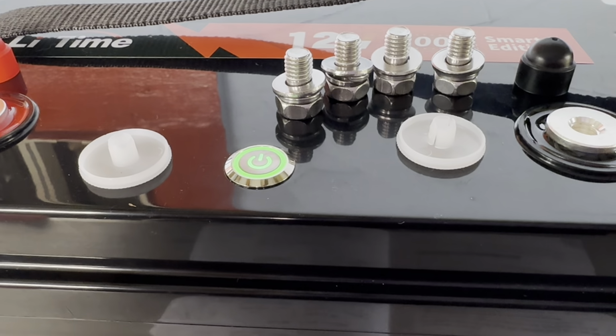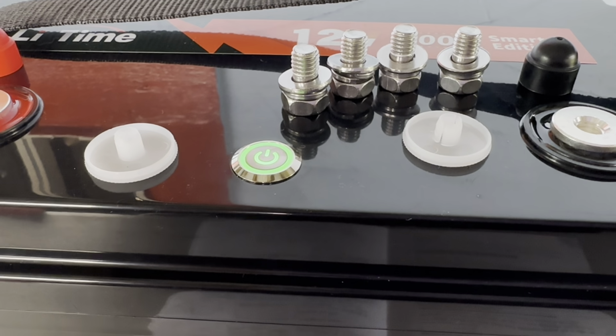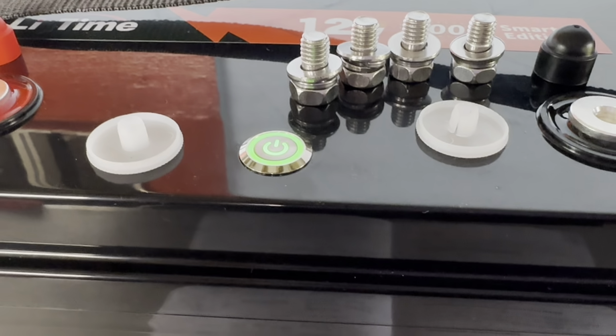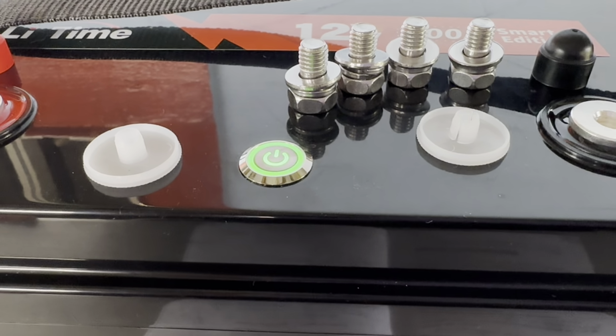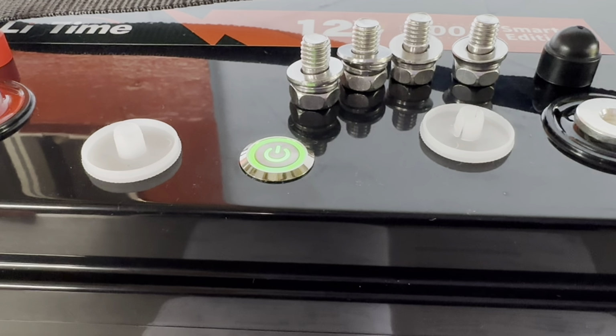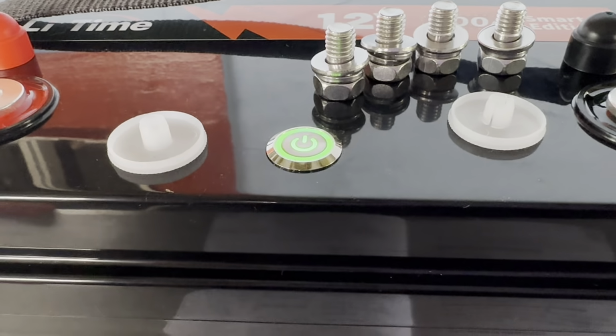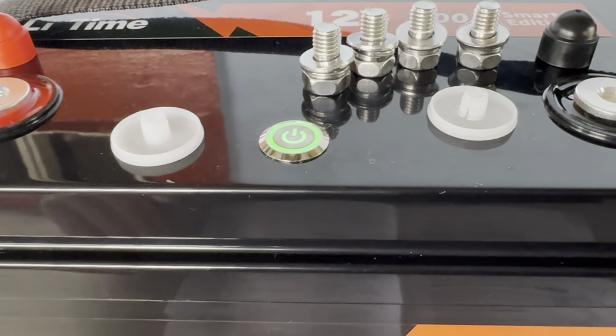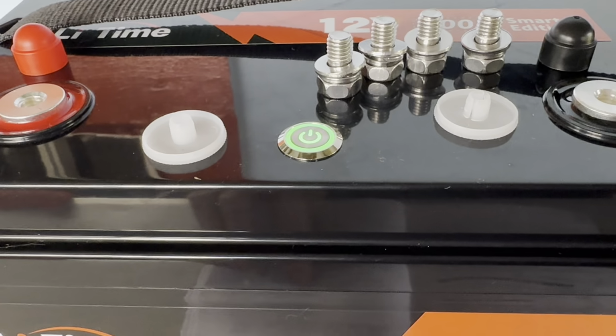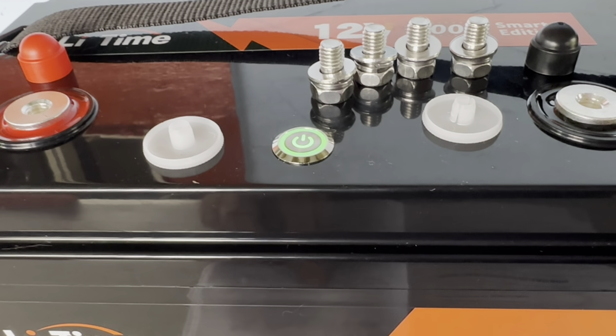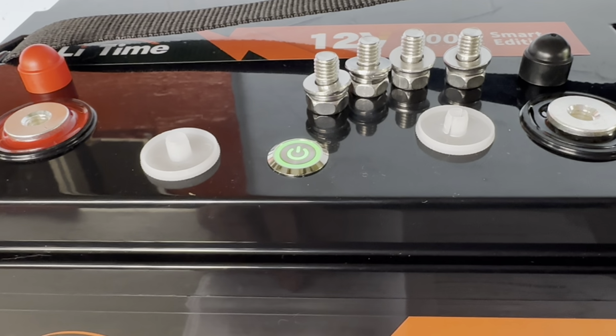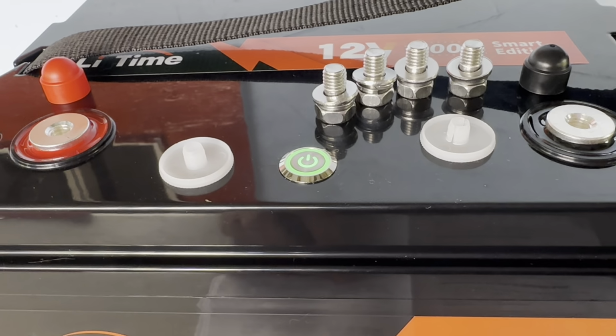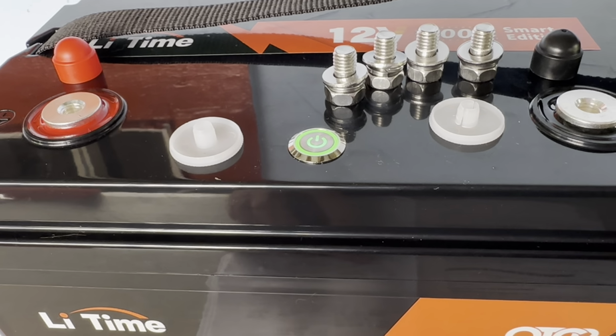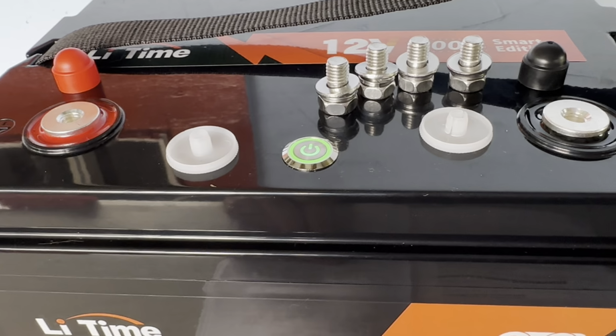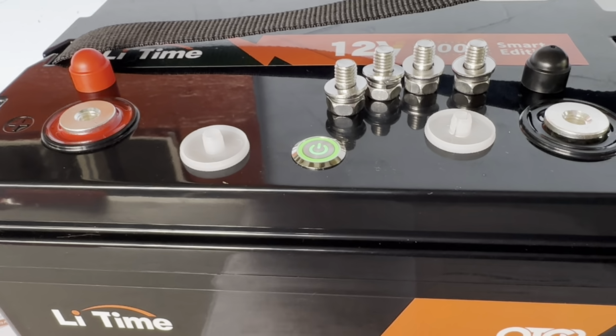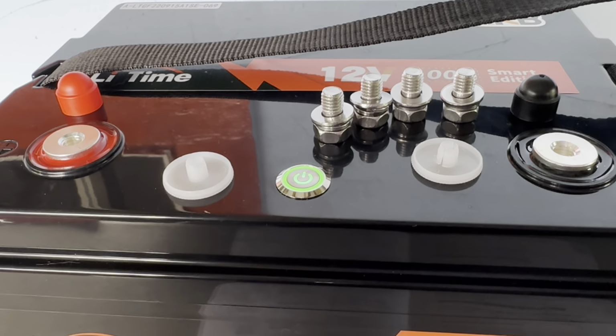And now if that red light was always on, it means that you have an abnormal cell voltage, or it could possibly mean that the battery is at the end of its normal life, and the battery will stop charging and discharging. A red flashing light would mean a BMS failure, and that could be for battery over discharge or battery over current. So then you would just wait for 30 seconds, switch from charging to discharging, or from discharging to charging to reset that BMS if that's what failed. So these are pretty nice little smart features, and they really are smart.